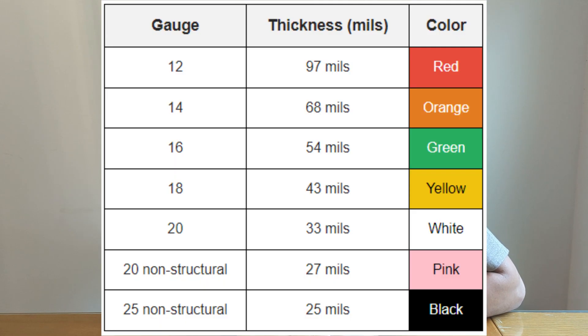Metal studs are often referred to by their gauge. They're available in a variety of different gauges which represents their thickness. The gauge value is measured in mils — thousandths of an inch. Common gauge options are 25, 20, 18, 16, and 14. The gauge greatly affects the stud's strength as well as the load bearing capacity — it's very important in design.